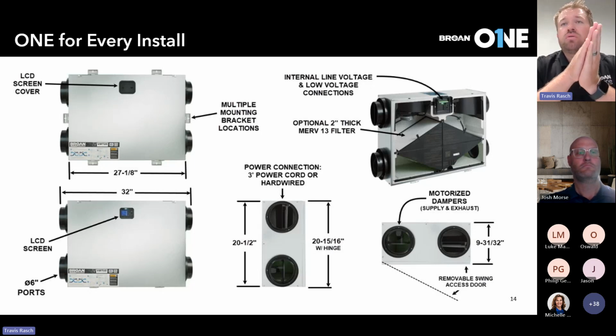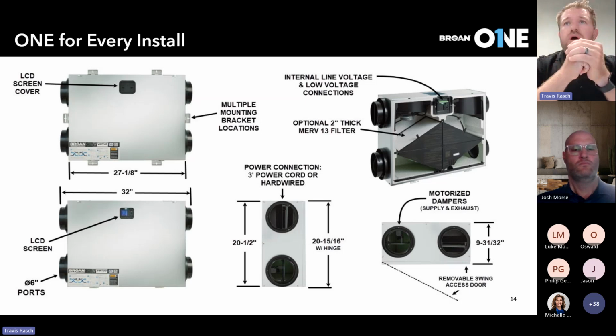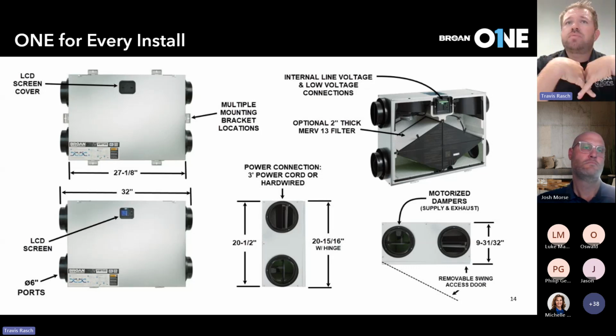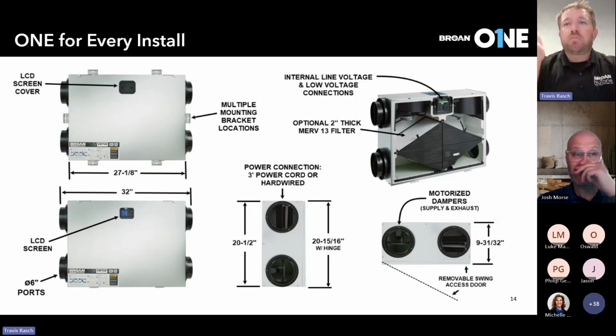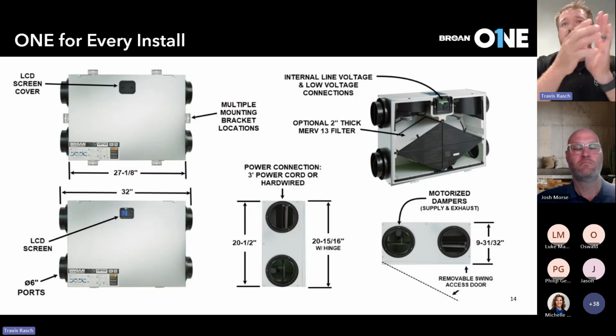So again, no external connections hanging off the side of the product. There are some codes and some local jurisdictions that, if you have any type of connection, whether it's for maintenance or for power, hanging off externally, will require a certain maintenance distance away from those. So if maybe this is behind an access door, and you have to have that additional 6 to 8 inches of maintenance access, your access door has now gotten significantly larger because you're having to accommodate that. That was one of the key drivers to get everything within that door opening, to minimize that access door, because we do know they're expensive, and also to minimize the penetration that we have in a ceiling assembly, as an example.